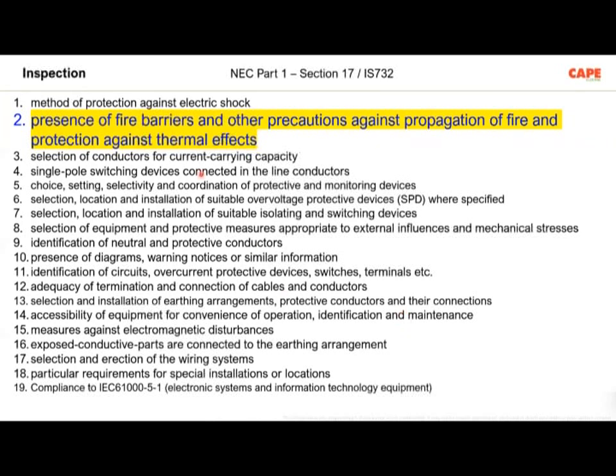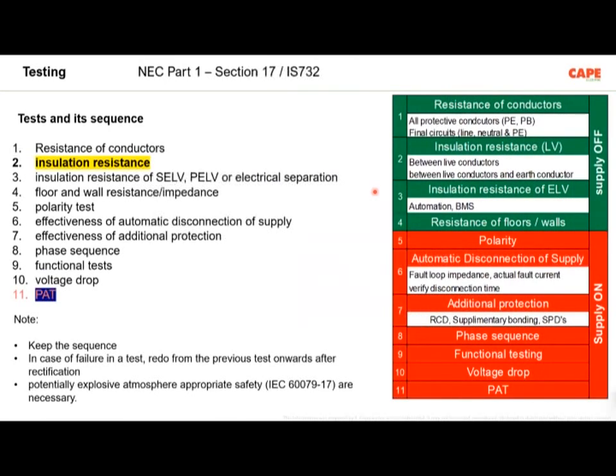I have put the inspection points 1 to 19, but all the 19 are not required sometimes. The last one, compliance to the EMC requirement, is not mandatory yet, but probably in future it will come. I will explain in detail the inspection point number 2, presence of fire barriers, other precautions against propagation of fire and protection against thermal effect. This I will explain a little bit later, but what you should understand is that there are 16 or 17 inspection points and there are 10 tests.